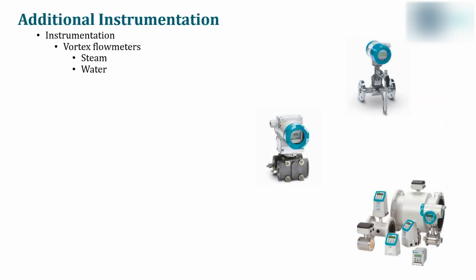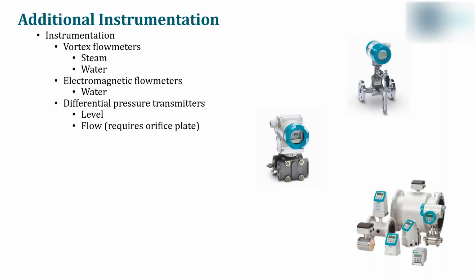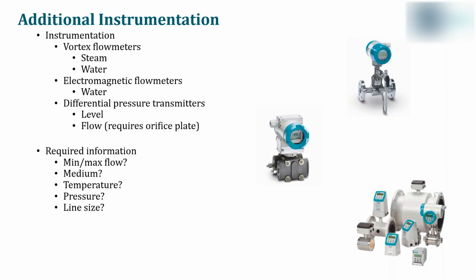Finally, additional instrumentation. Siemens does offer additional instrumentation, especially in a boiler room. There's instruments all around us. We do offer vortex flow meters, which are primarily used for water and steam, electromagnetic flow meters, which are used for water, and finally, differential pressure transmitters, which we use for level or flow. But when you're dealing with flow, you do require an orifice plate.